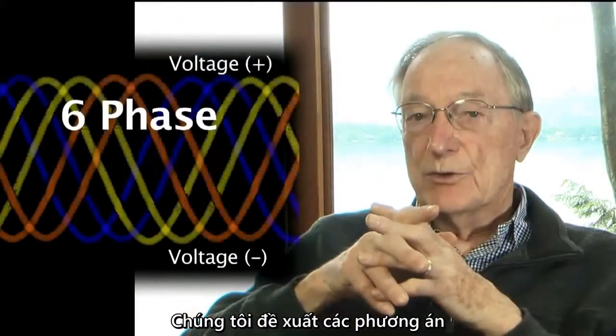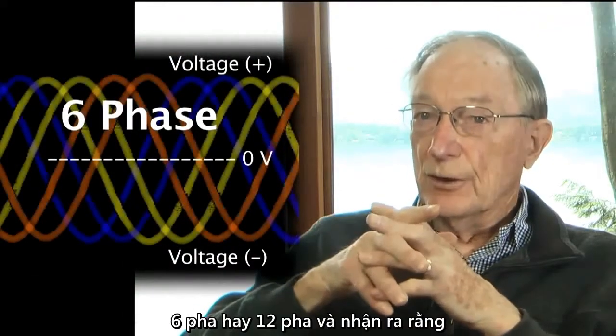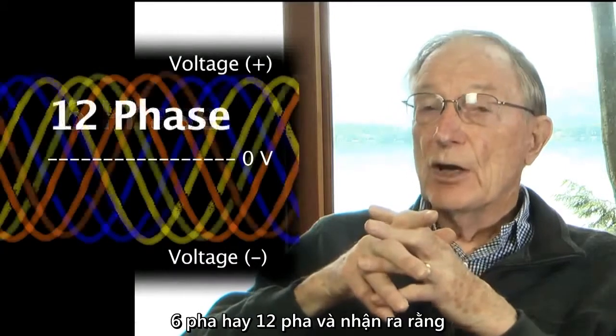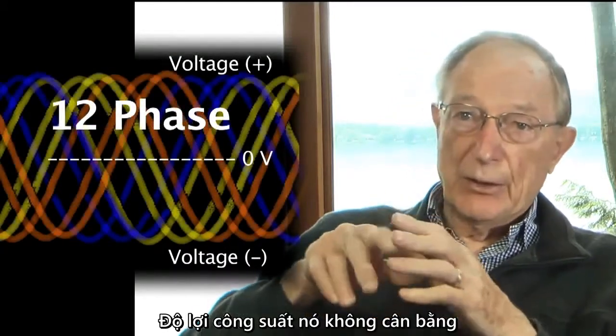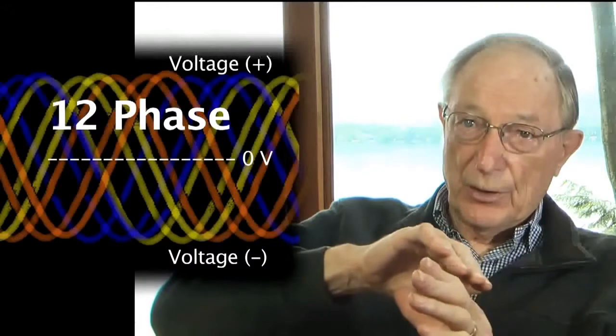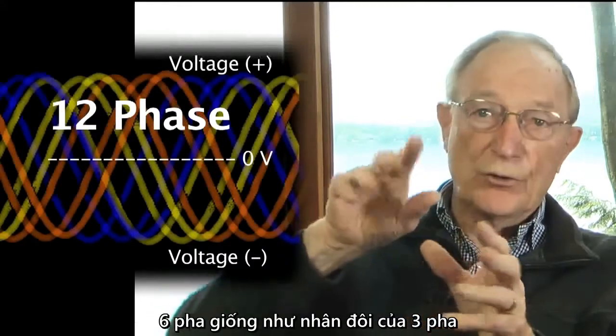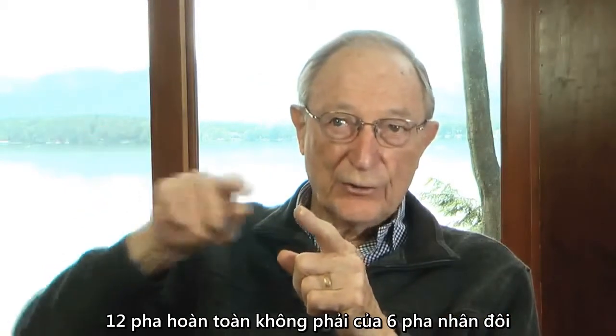we proposed some serious look at the 6-phase and 12-phase line. It turns out that the gain in power is not proportionate. 6-phase almost doubles 3-phase. 12-phase does not almost double 6-phase, so it's a diminishing return.